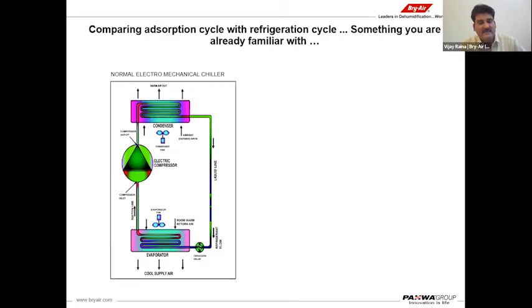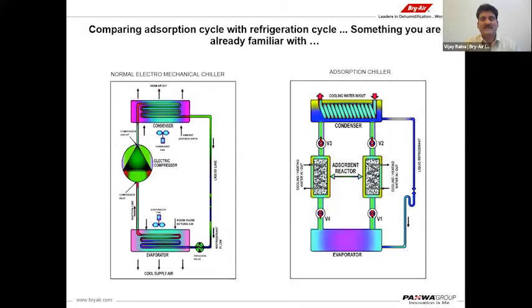Everybody knows that a refrigerant takes the outside cooling load and throws it out through the condenser. So this refrigerant is moving from one heat exchanger to another in a closed loop with the help of the compressor. The compressor is the heart of a mechanical chiller, whether it is screw, centrifugal, scroll, whatever technology is available as of date. Our technology is now to replace this compressor, where huge energy is consumed, by using silica gel, and the purpose of silica gel is the same as what the compressor is doing, transferring refrigerant from one heat exchanger to another. The same way we are transferring our refrigerant from the evaporator and through silica gel, and finally it goes into the cooling water side and the heat gets dumped outside in the cooling tower.